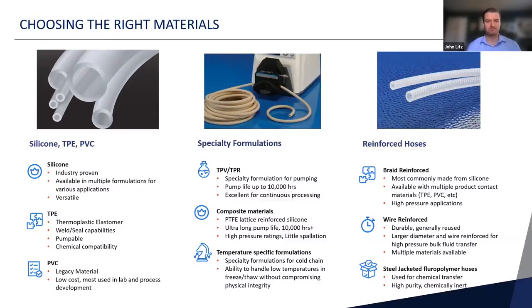Composite materials are also something you might commonly see on the market. And here, the main example that I'm thinking of is going to be a Stay Pure tubing. That is, again, a specialty formulation that can withstand very high pressures with little to no particle shedding or spallation in process. And again, it's going to have ultra long pump life of 10,000 hours plus. And some of the ways that they might be manufactured, composite materials or Stay Pure for this example, is if you're utilizing silicone and a PTFE, the PTFE would be essentially done via scaffold, and then the silicone would fill those gaps, ensuring that that composite material is made correctly. There's going to be a really great use case in pumps. There's going to be very high pressure tolerances for any type of very critical application that you're going to be running pumps for a very long extended period of time.